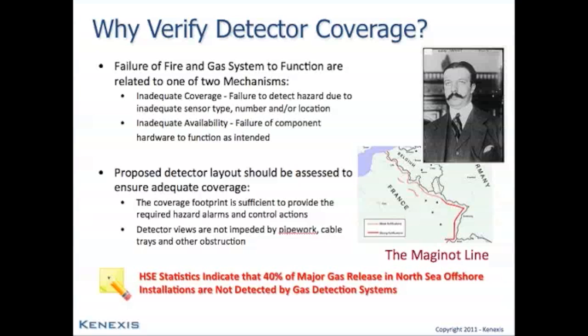So in order to ensure that the detector layout coverage is adequate, it will need to be assessed. You need to ensure that the footprint of the coverage, meaning the area at a certain level of elevation that the fire and gas detection array can see, is adequate to provide the required alarms and control actions for the given scenarios in that zone. Also, it's important to ensure that the detector views are not impeded by pipework, cable trays, or other obstructions. Those obstructions need to be considered in 3 dimensions when the coverage analysis is being performed.